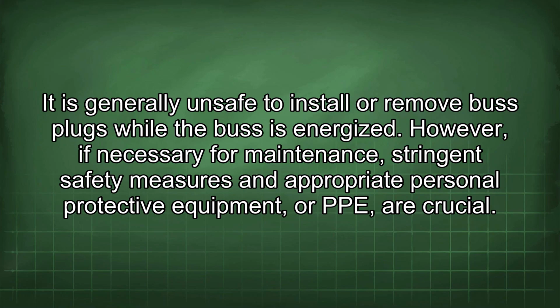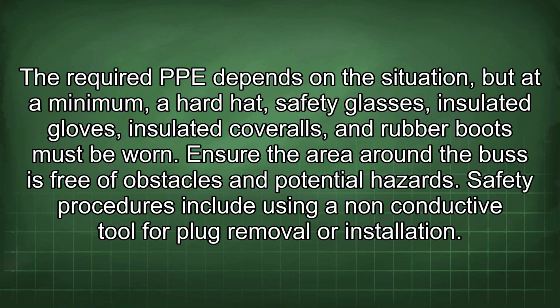It is generally unsafe to install or remove bus plugs while the bus is energized. However, if necessary for maintenance, stringent safety measures and appropriate personal protective equipment, or PPE, are crucial. The required PPE depends on the situation, but at a minimum, a hard hat, safety glasses, insulated gloves, insulated coveralls, and rubber boots must be worn.